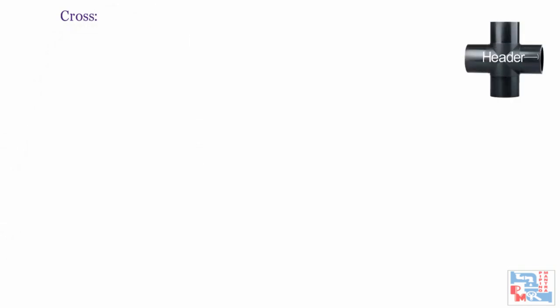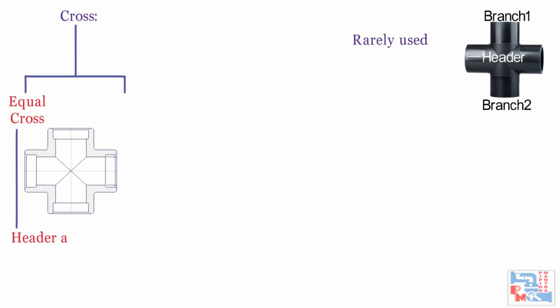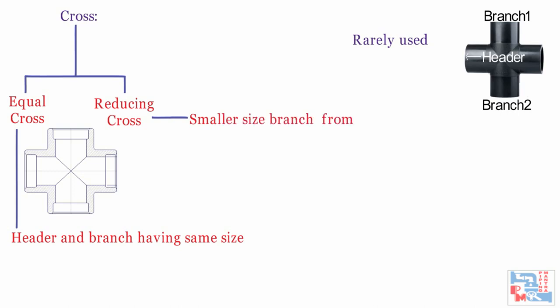The next fitting is the cross. It is used to have two branches connect at the same point on the header — basically a 4-way fitting. This fitting is very rarely used in piping systems. There are two types: straight or equal cross, with header and branch connections of the same size; and reducing cross, with smaller branch connections. It is preferable to use Ts except where space is restricted, as in marine piping.